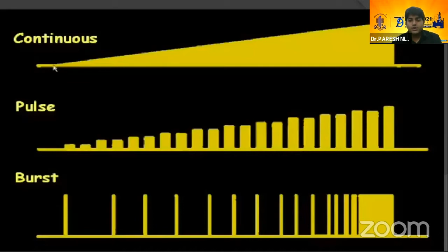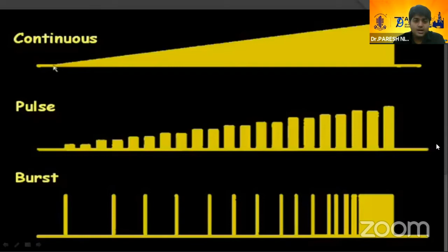One is the continuous mode, in which the power increases as we go forward in foot pedal stage 3. In pulse mode, the interval between on and off is decided, and the energy increases as we go forward in stage 3. In burst mode, the energy dissipated is kept constant, but as we go forward in foot position 3, the interval between the on and off cycle decreases, and at the end of foot position 3, it basically turns into a continuous phaco mode.